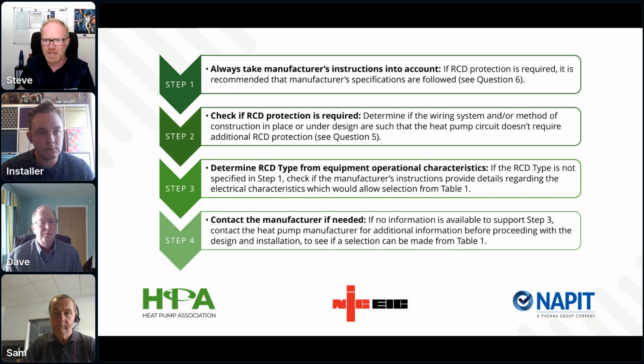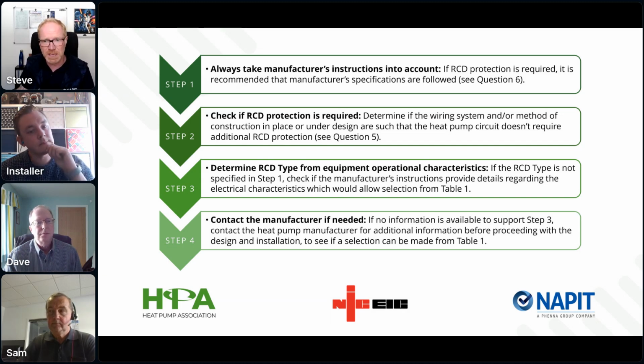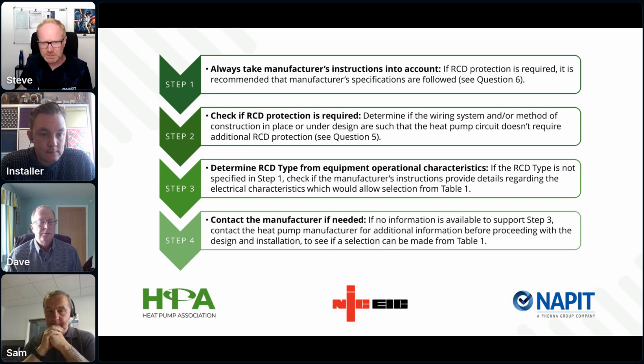So where the cables in the circuit have mechanical protection from screws, so let's say it is buried deeper than 50 mil, or it's got earth metal armor, an SWA cable, it's put in metal conduit or metallic trunking, it could allow the designer to negate the need for an RCD in those circumstances. So although I just read out that product standard that said it's advisable, this is sort of not the get out of jail card, because that's the wrong term to use, but this is the reason where sometimes it's not always necessary. And we do quite a lot of this in solar PV. We do talks where we recommend if you could design out, excuse me, an RCD because of things like the nuisance tripping we've just talked about, then there might be circumstances where you can.